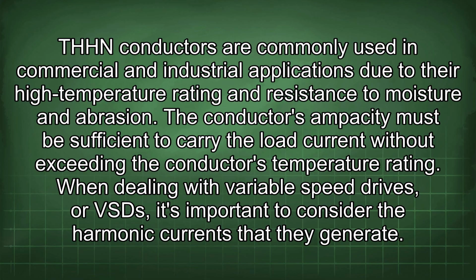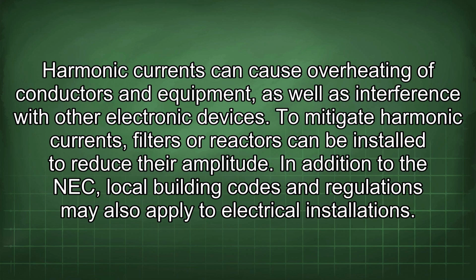When dealing with variable speed drives, or VSDs, it's important to consider the harmonic currents that they generate. Harmonic currents can cause overheating of conductors and equipment, as well as interference with other electronic devices. To mitigate harmonic currents, filters or reactors can be installed to reduce their amplitude.